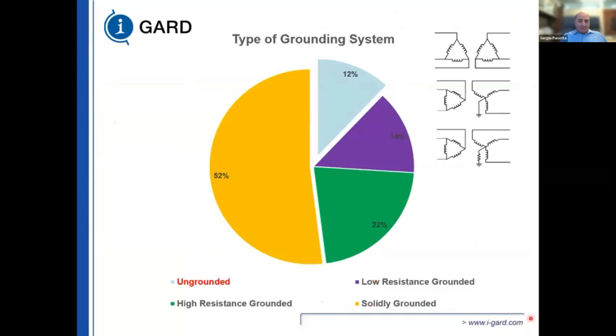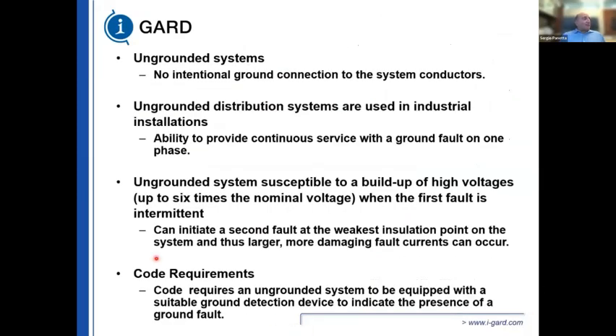We're going to start with ungrounded systems first, because most systems were ungrounded systems. There's no intentional ground connection between the system conductors and ground. Ungrounded systems are susceptible to buildup of high voltages, up to 6 to 8 times normal system voltage phase to ground, that were typically phase to phase. On a 480 or 600 volt system, you can easily get 6 to 8 times overvoltages with respect to ground when you have an intermittent ground fault. Code requires ungrounded systems to be equipped with suitable ground detection systems. There is no ground fault protection in an ungrounded system. The only thing you could possibly have is ground fault detection.